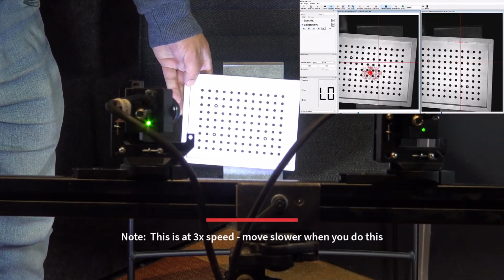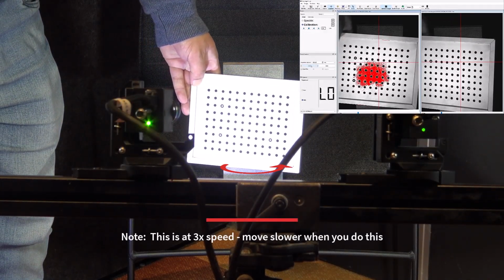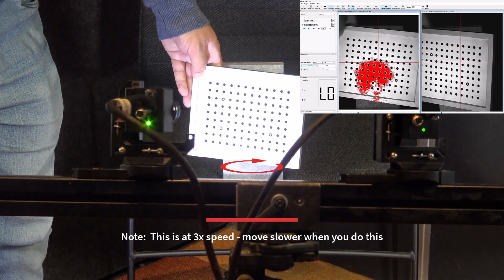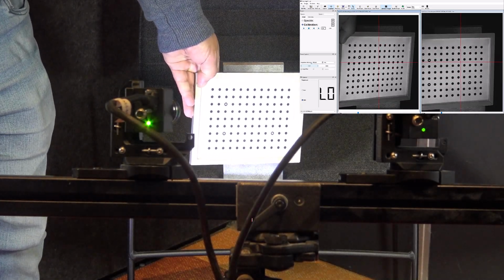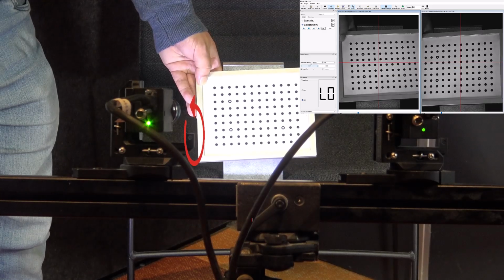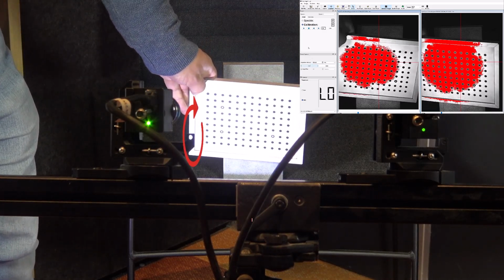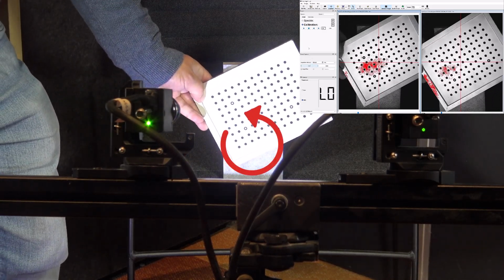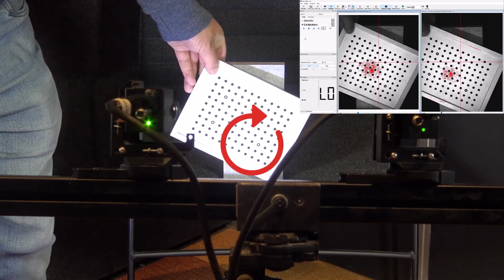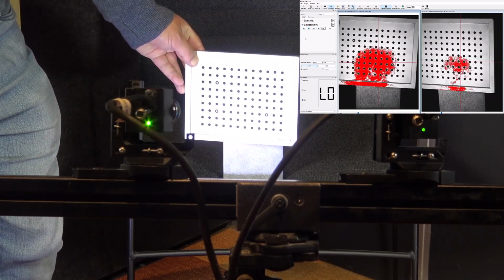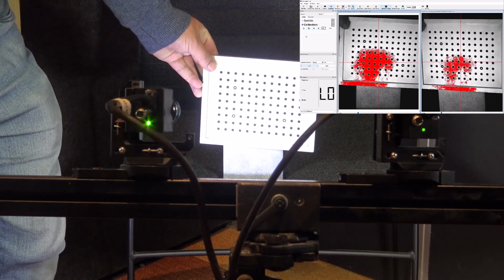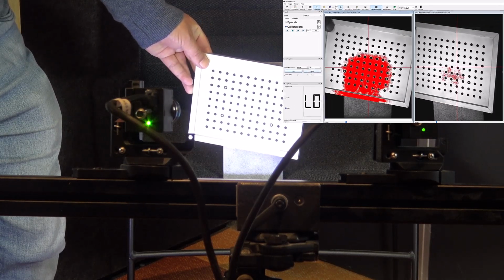After hitting start for timed capture, the procedure here is to get the cameras capturing images while we rotate the calibration plate around all three axes. Be careful to move slowly enough so that we don't get motion blur, and pay close attention to the three special dots on the plate, as we don't want those dots to fall off the images of either the left or the right cameras. Stop capturing when you've done all of your rotations. Ideally, you'll have in the vicinity of about 100 images taken when you're all done.